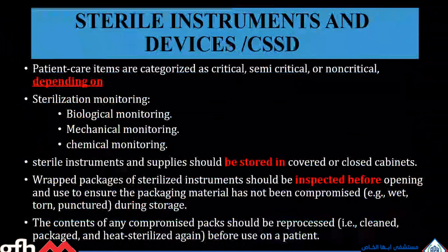Number one, I should inspect before opening whether the package is wet, torn, or punctured. I will check whether the chemical indicator passes or not, and check whether the instrument inside the bag is clean or not. All these items are the responsibility of the end users to check.